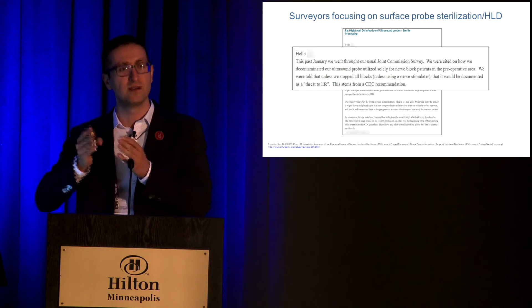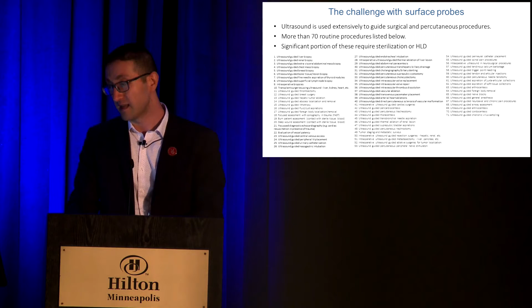More impact. Okay. So this particular slide, when I looked at it, and the screen was 2 inches in front of me, I couldn't even read those 71 procedures. So if you could tell me what number 40 is, that'd be great. But the takeaway from the slide is that there are over 70 ultrasound probe procedures done, minimum, and a significant portion of these require high-level disinfection or sterilization because of how they are used.